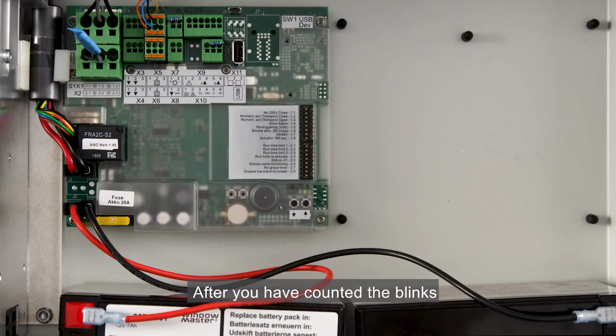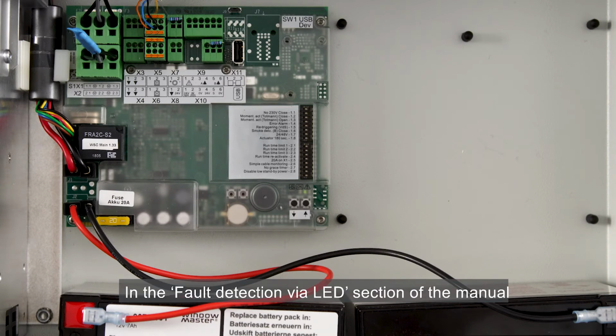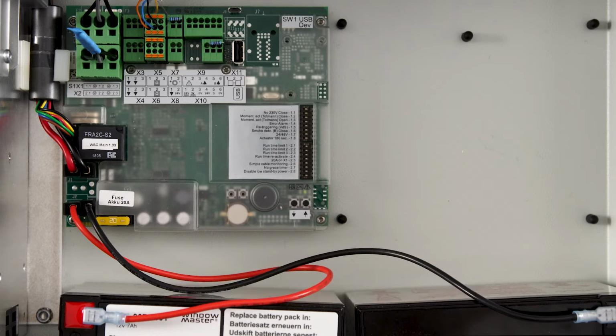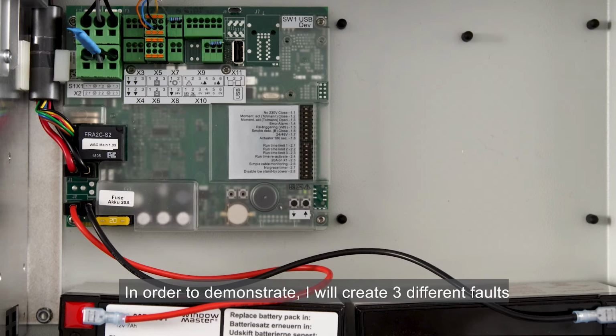After you have counted the blinks, you must look at the instruction manual for the interpretation of the blink sequence. In the fault detection via LED section of the manual, you'll find a table with the list of blink sequences and the corresponding fault descriptions. In order to demonstrate, I'll create 3 different faults.